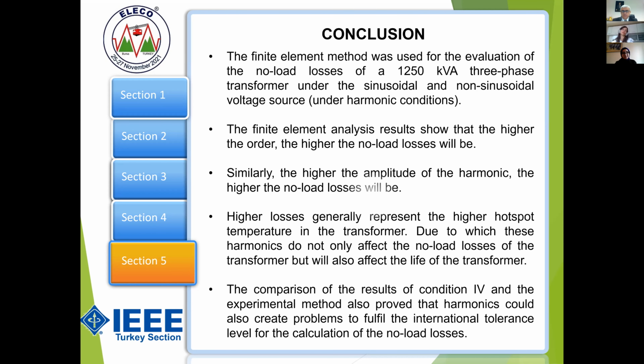So let's conclude our work. In this work, we have used a 1250 kilovolt-ampere three-phase transformer under sinusoidal and non-sinusoidal voltage sources. The finite element analysis of our results shows that higher order harmonics generate higher no load losses. As compared to the third, the fifth makes more no load losses. And we can come to another result: higher losses generally mean a higher hotspot temperature in the transformer, as I told previously, due to which these harmonics not only affect the no load losses, but the overall life of the transformer can also be decreased.